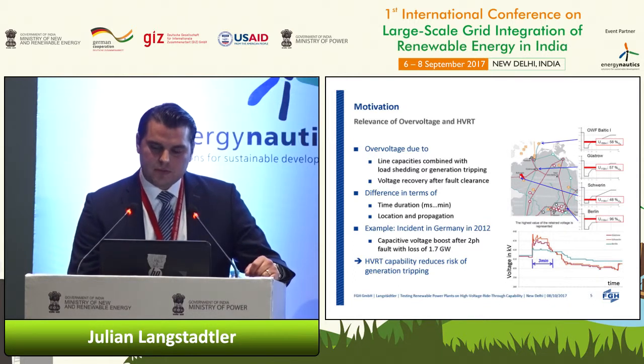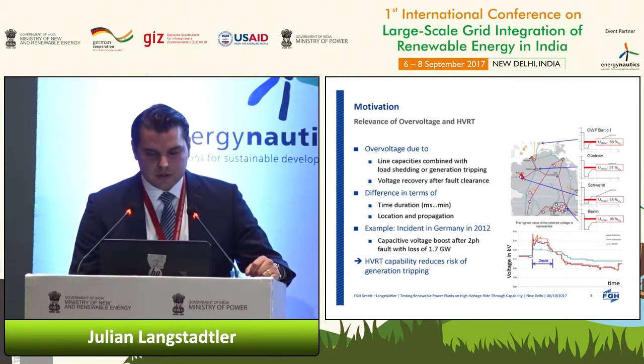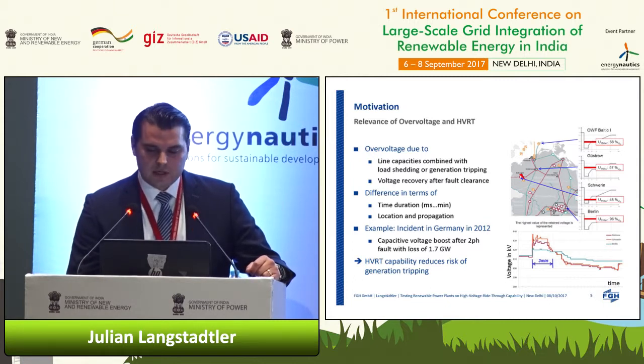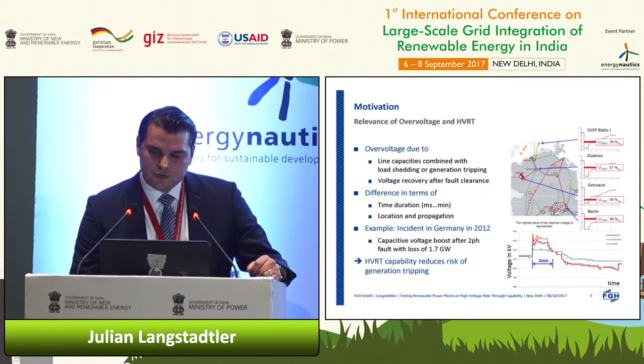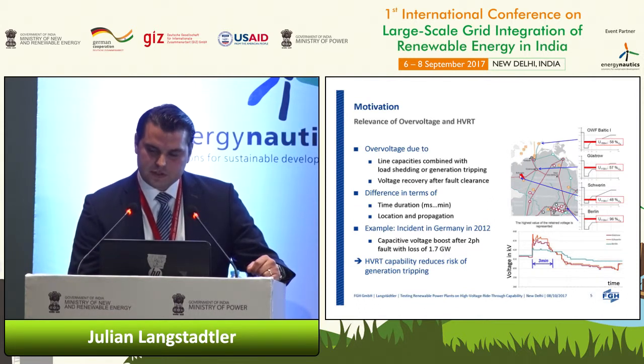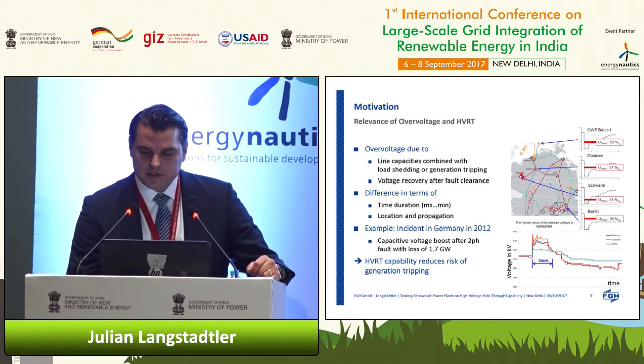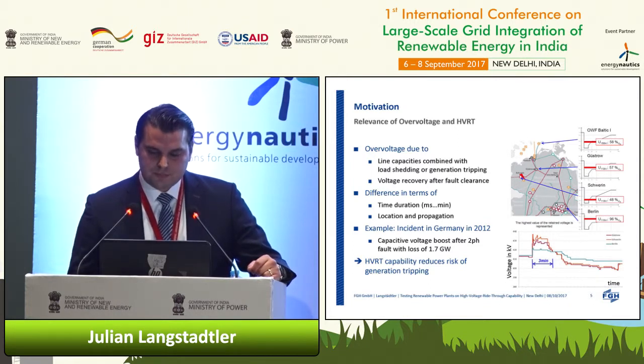And in this system, there was a short circuit, a two-phase fault on a transmission line in the extra high voltage system. And the voltage dip expanded over the system itself. And you see here that even the wind farms, so the offshore wind farm here on the Baltic Sea, were affected with a voltage sag of almost 60%, whereas at the fault location in the 110 kV system, we even had voltages down to 48%.